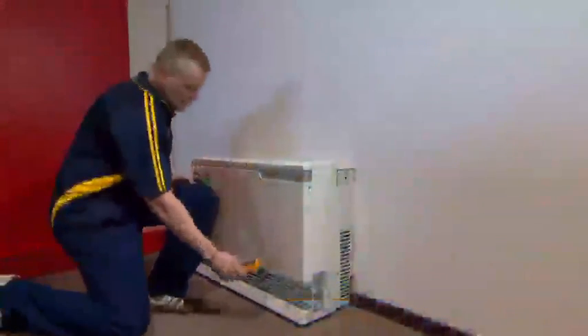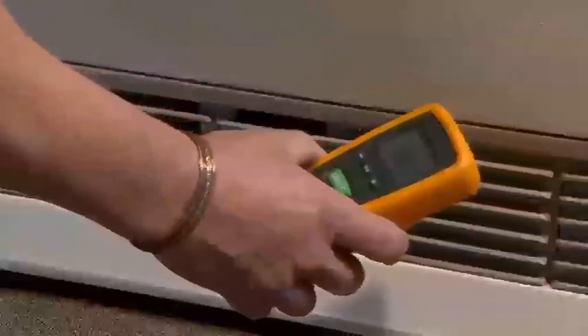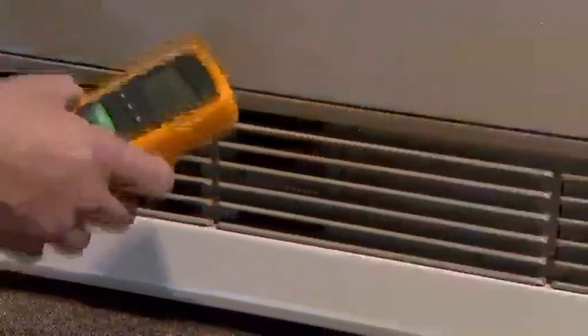Always check lower levels of room-sealed gas space heaters, as these appliances may incorporate a condensate drain at the base of the heat exchanger, and this could be an area where combustion products may discharge into the building.